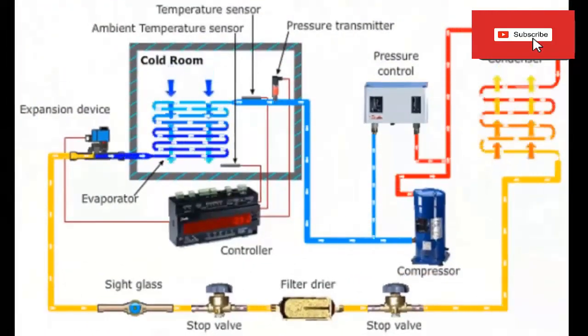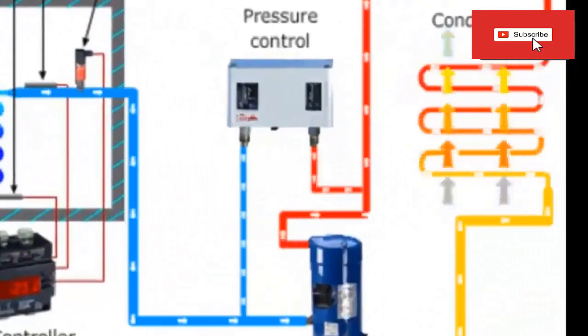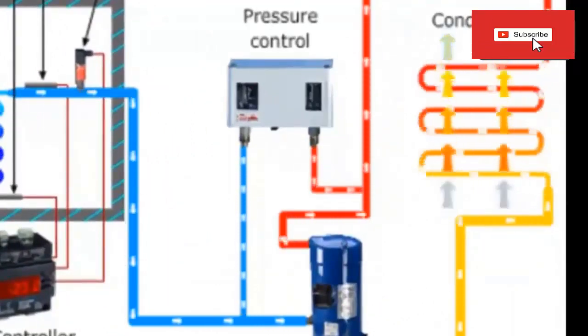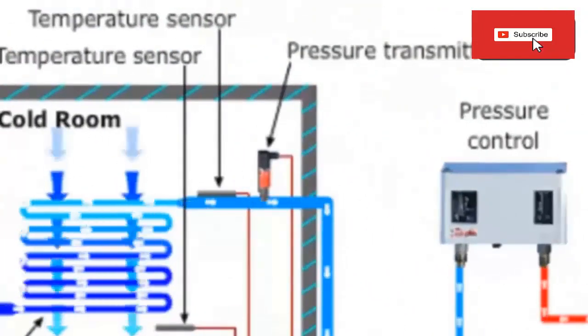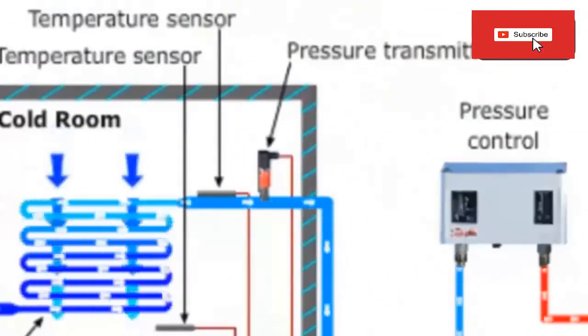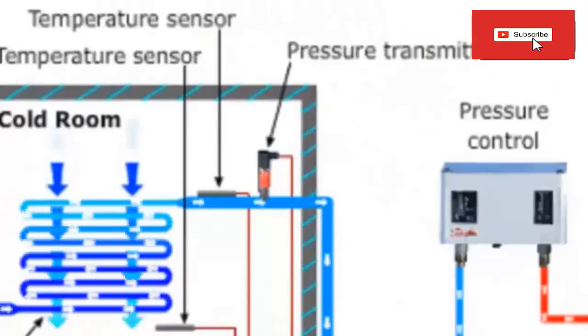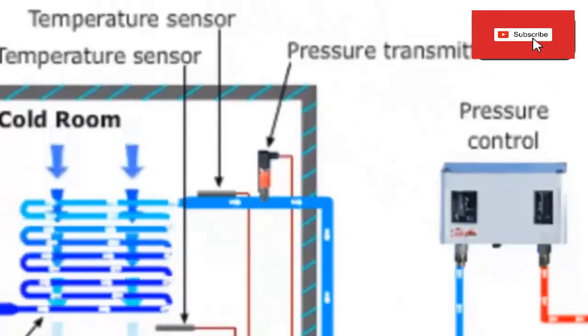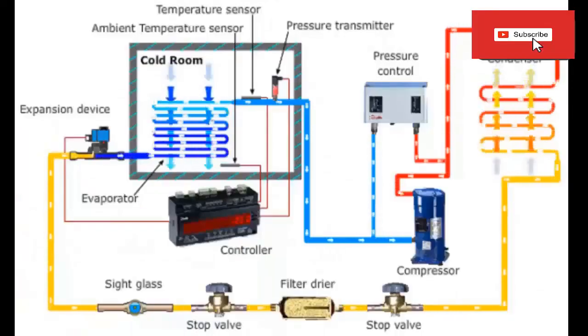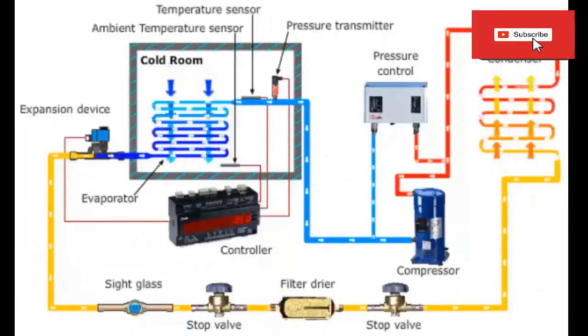We also observe the control and safety mechanisms. Pressure switches stop the equipment due to low pressure in the compressor suction or due to high pressure in the discharge of the system. A pressure transducer for the suction line is used to inform the electronic controller of the pressure value, using electronic signals of the analog or digital type.